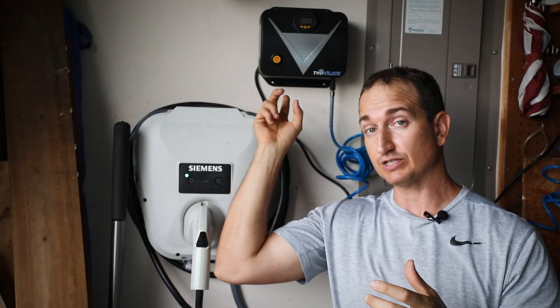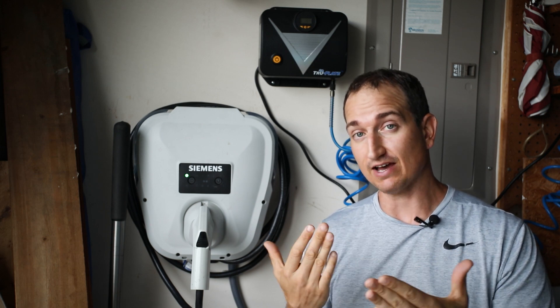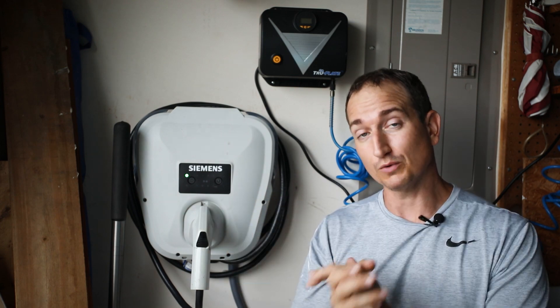So basically the vibration from this would have maybe caused the tensioner screw in the bus bar to slowly loosen over time, and maybe I did have a little bit of gap in there creating that high heat situation that was problematic where this thing started to melt.